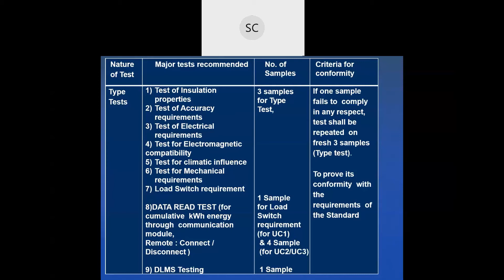Now, IS, what are the applicable standards? Again, same thing I have repeated here, sir. Static meters are covered by IS 16444 Part 1, both single phase or three phase. Part 2 is for low current meters, and this is for transformer operated meters. Transformer operated means maybe a CT or maybe a PT, sir, anything. And load switch requirements: in these standards, Part 1 and Part 2, load switch is not there.